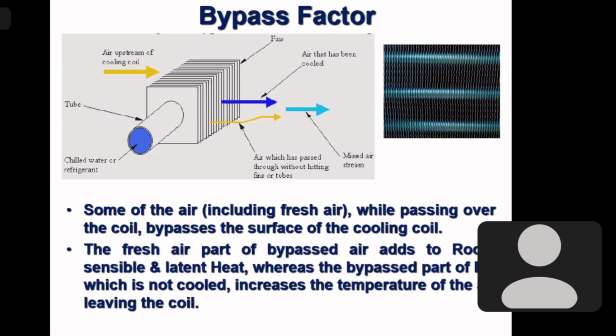The fresh air part: we consider this bypass air in two parts. One is the fresh air part, because the air which bypasses the cooling coil is a mixture of outdoor fresh air and return air. So, for our easier calculation effort, we split it into two parts. One is the fresh outside air, which is hotter than the return air. If we set the room temperature at 24 degrees centigrade, then the return air temperature will be 24 degrees centigrade. But the outside air, like in Calcutta a few days ago, was 42, 43 degrees centigrade.